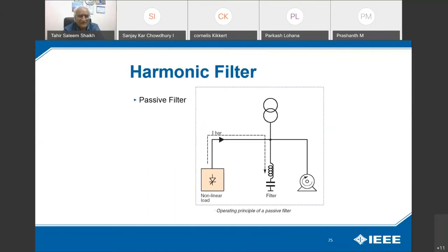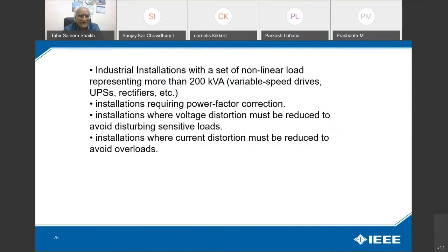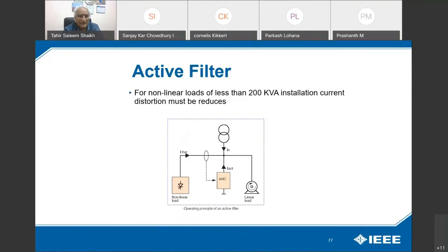This is a passive filter, used in industrial installations with a set of nonlinear loads representing more than 200 kVA: variable speed drives, UPS, etc. Such an installation requires power factor correction, where voltage distortion must be reduced to avoid disturbing sensitive loads, or where current distortion must be reduced to avoid overloads. Active filters and hybrid filters are very expensive. Active filters are for nonlinear loads of less than 200 kVA, where current distortion must be reduced.